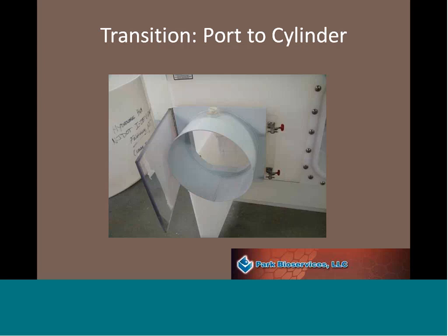So another alternative that we have for people that had isolators with rectangular ports and didn't have the round port configuration: we've made adapters, so you can adapt something that was made with just a rectangular door, and now with the adapter, you can link up a cylinder. Or the other use that this is used for is in the case of the Taconic germ-free shipper. You can link a germ-free shipper to this port adapter and introduce your animals aseptically.